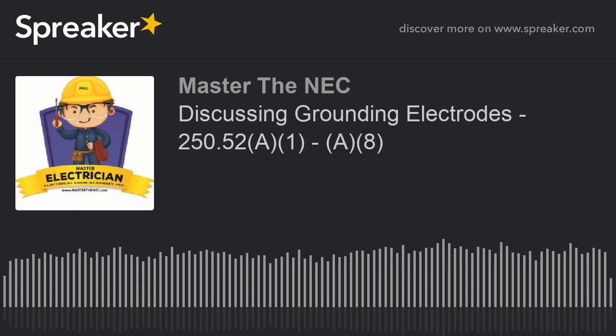Okay? Next is A5, dealing with rod and pipe electrodes. Now, this is ground rods, or it could be an actual pipe that's driven. Back in the old days, it used to be real common to drive pipes down into the ground. Okay? Now, let's look at it. Rod and pipe electrodes shall not be less than 8 foot in length. Okay? Could it be more? Obviously, yes. We've seen 10 foot. Okay? But it can't be less than 8 foot in length and shall consist of the following material.